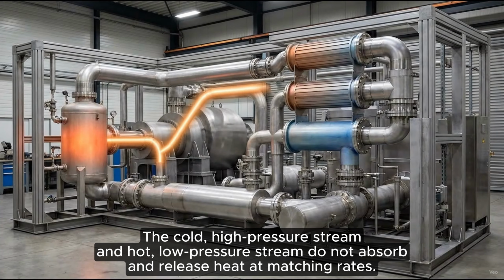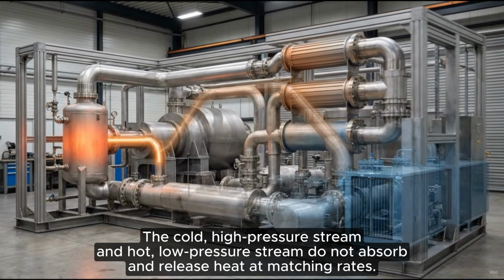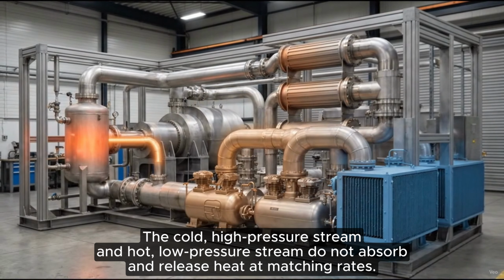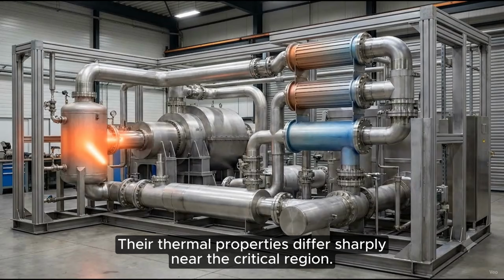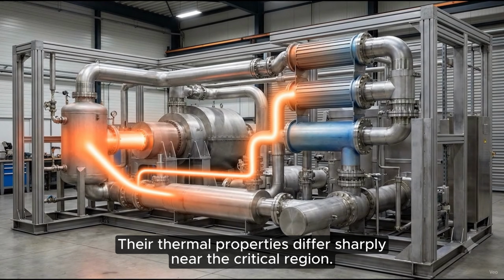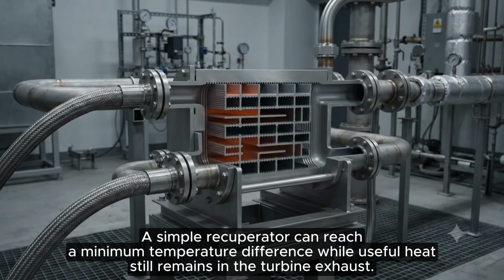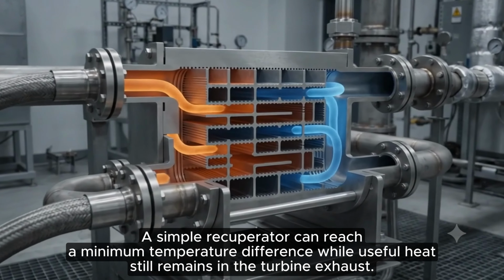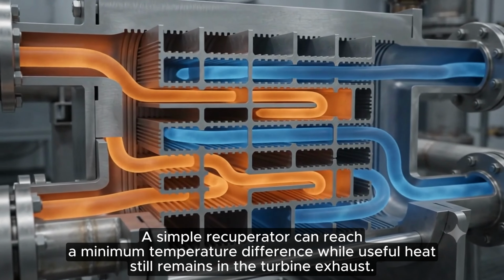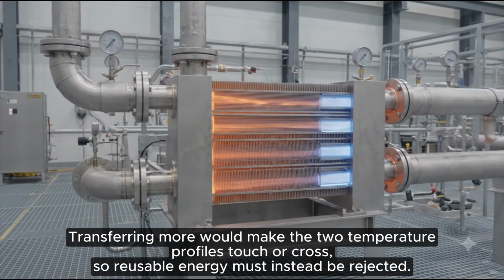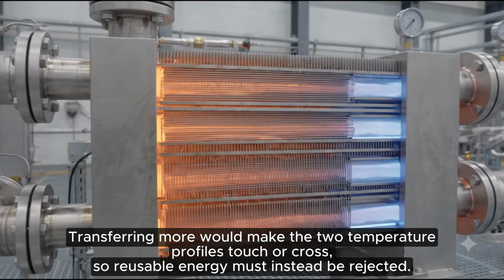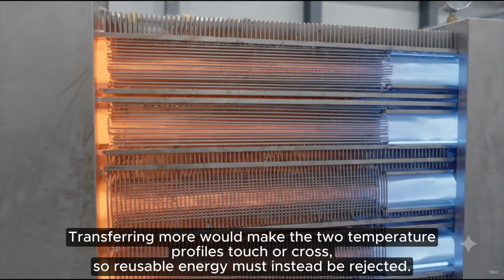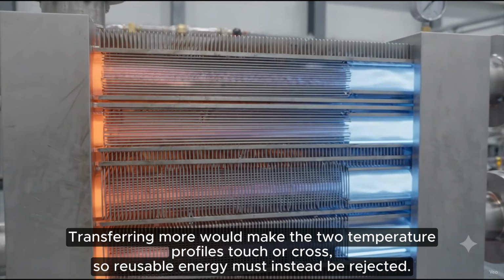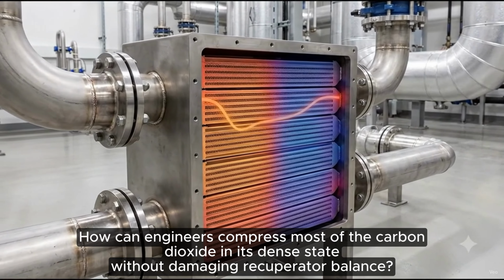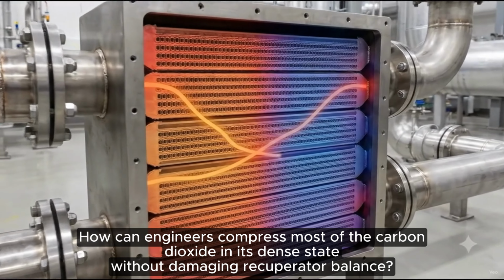The cold, high-pressure stream and hot, low-pressure stream do not absorb and release heat at matching rates. Their thermal properties differ sharply near the critical region. A simple recuperator can reach a minimum temperature difference while useful heat still remains in the turbine exhaust. Transferring more would make the two temperature profiles touch or cross, so reusable energy must instead be rejected. How can engineers compress most of the carbon dioxide in its dense state without damaging recuperator balance?